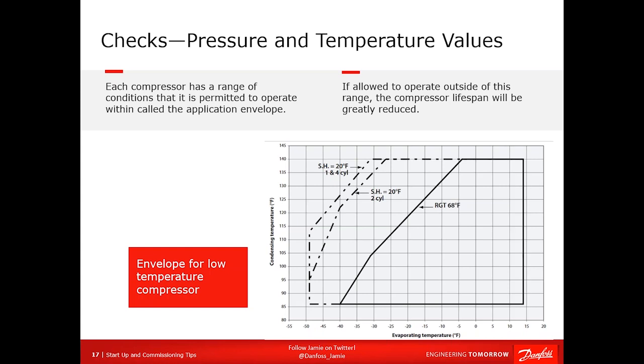However, if your superheat exceeds 20 degrees, and it ain't hard, picture an ice cream freezer running at minus 20, right? You run the suction line through an unconditioned space with crappy insulation, you're going to pick up another 40 or 50 degrees of superheat pretty darn quick, right? So now the gas coming back to the compressor isn't minus 20 plus 20, 0. It's more like 40 or 50 degrees Fahrenheit, which means your application envelope is now a lot smaller. And this is what happens with loss of charge.